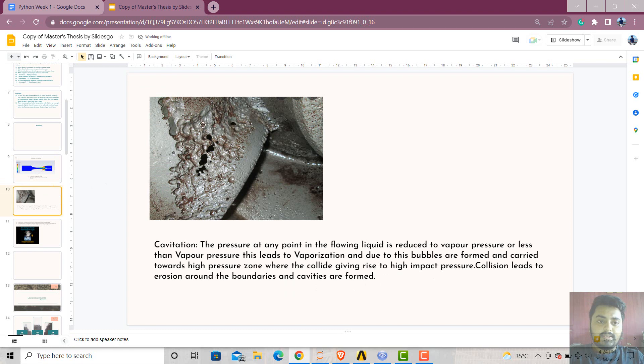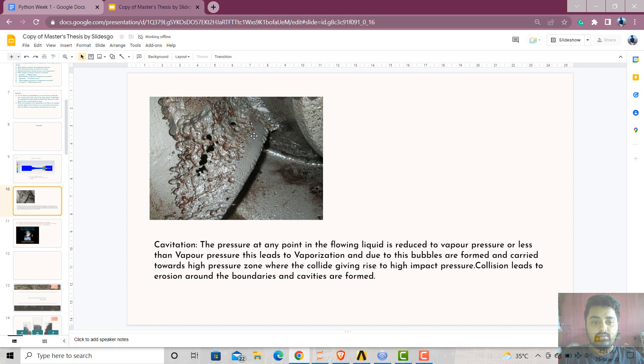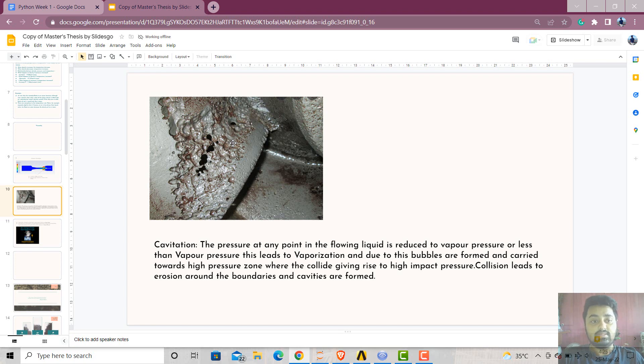I will show you a live example. In the industry, this turbine was affected by cavitation. This is the result of the cavitation process. The cavitation process is nothing but: the pressure at any point is reduced to vapor pressure or less than vapor pressure, which leads to vaporization. Due to this, the bubbles are continuously forming and are carried towards the high pressure zone. When these collide with each other, they produce high impact pressure. Just because of this, the erosion process takes place and the cavities are formed. This can be pretty harmful in every industry. Examples where the cavitation process takes place are turbines, pumps, and anywhere liquid is continuously flowing.